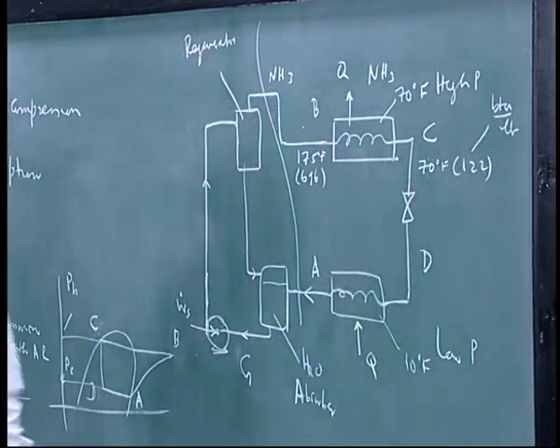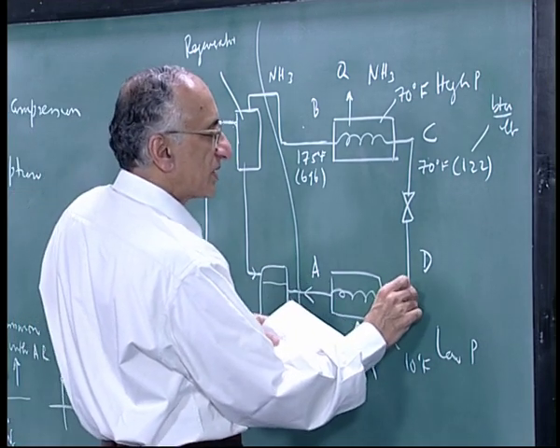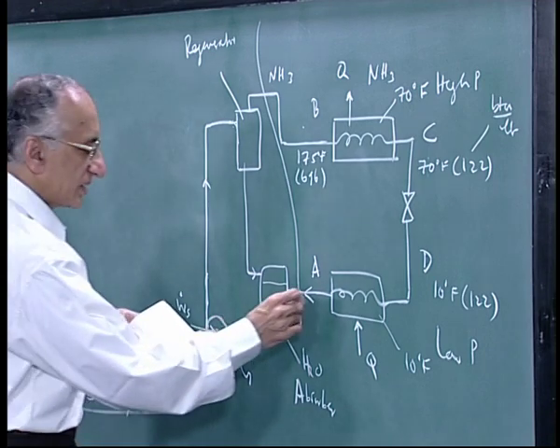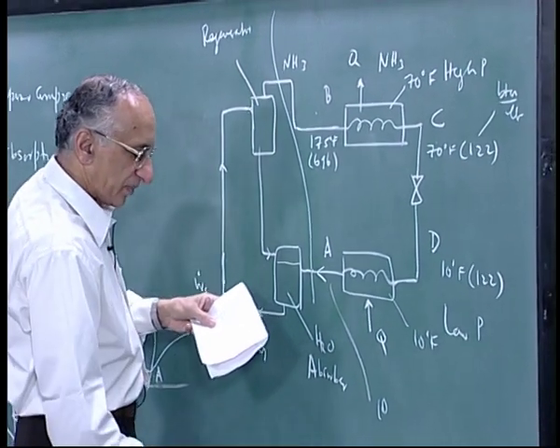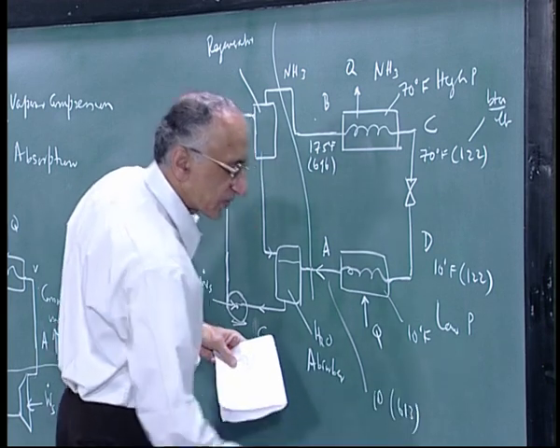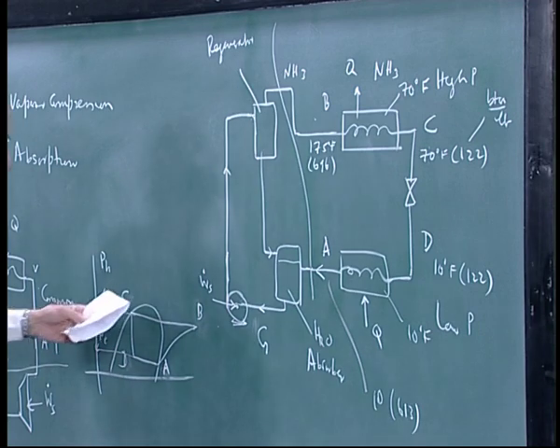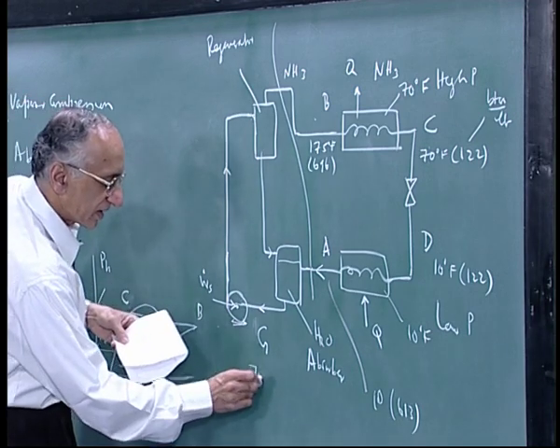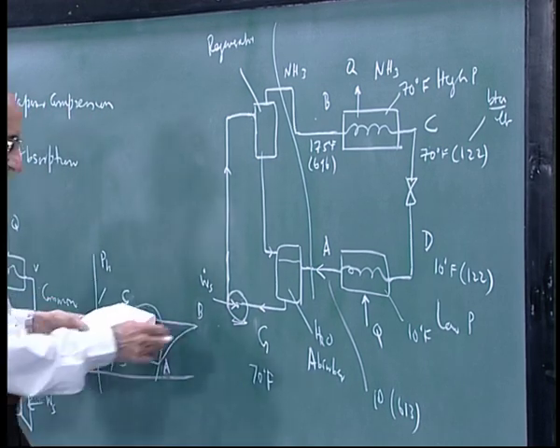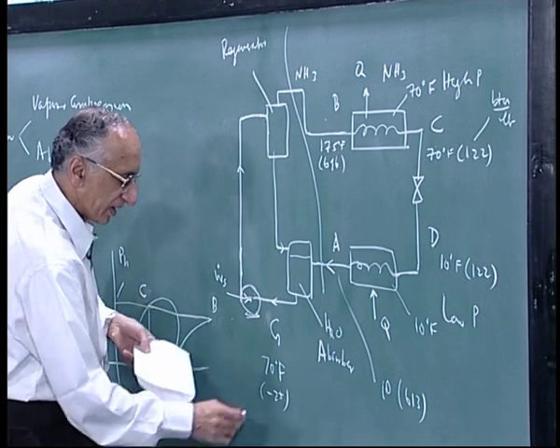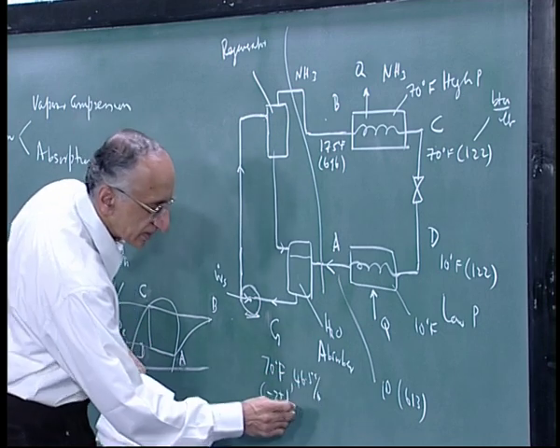At point C (70°F, 128 PSI), enthalpy is 122 BTU/lb. After throttling, point D is at 10°F and enthalpy remains 122 BTU/lb (isenthalpic). After heat absorption in the evaporator, point A is at 10°F with enthalpy 613 BTU/lb — that represents the latent heat of evaporation of ammonia. After absorption, the temperature rises to 70°F with enthalpy minus 25 BTU/lb, and the concentration is 46.5% ammonia by weight.